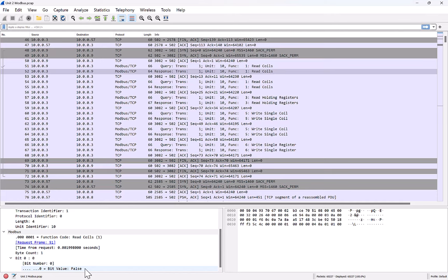Now, in the PLC world, that can mean anything. But let's say maybe that's the value for whether you have the run switch enabled on that PLC or not. The run switch puts essentially the PLC into read-only mode, so that way you can't make changes to it. You can't upload firmware, you can't change the PLC programming, which also means an attacker can't make those changes. So we want to make sure PLCs, when they're running, when they're not being programmed, when they're not being updated, we want to make sure that that switch is set. And so we want to make sure that in this case, we might see that that value says false and no, that switch is not set. So we need to go into the field and set it.